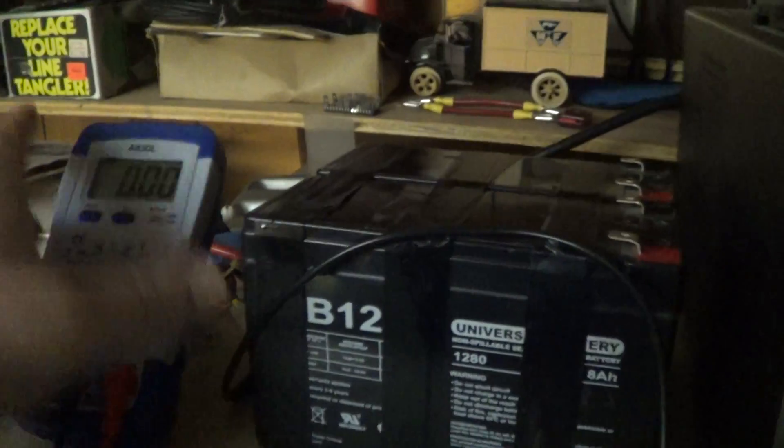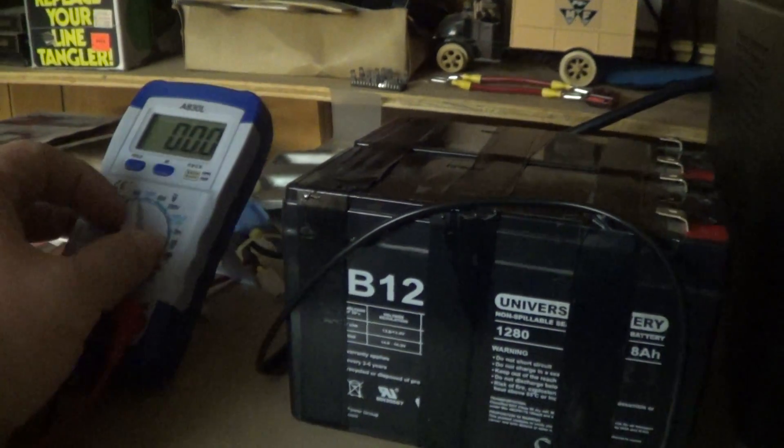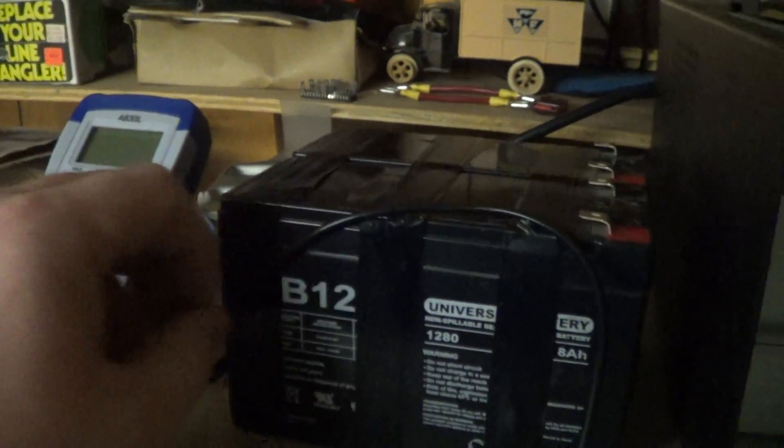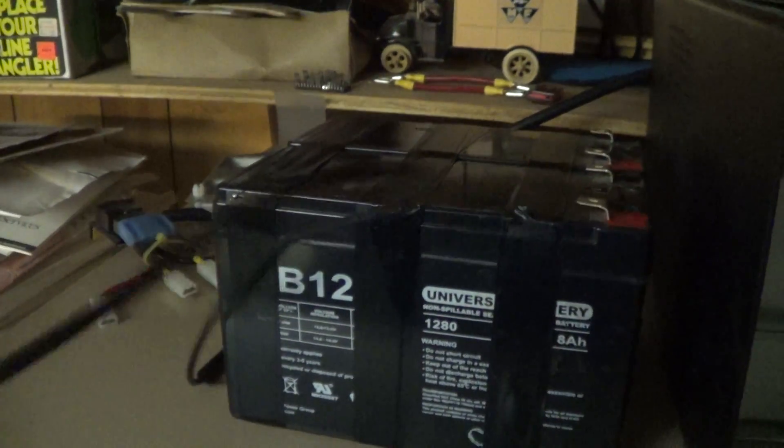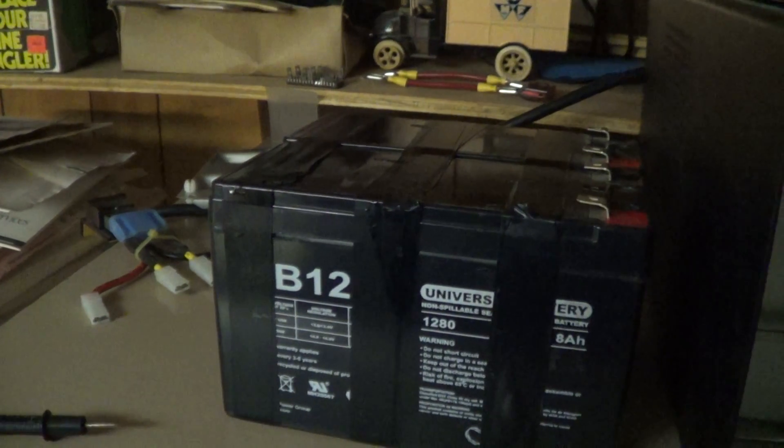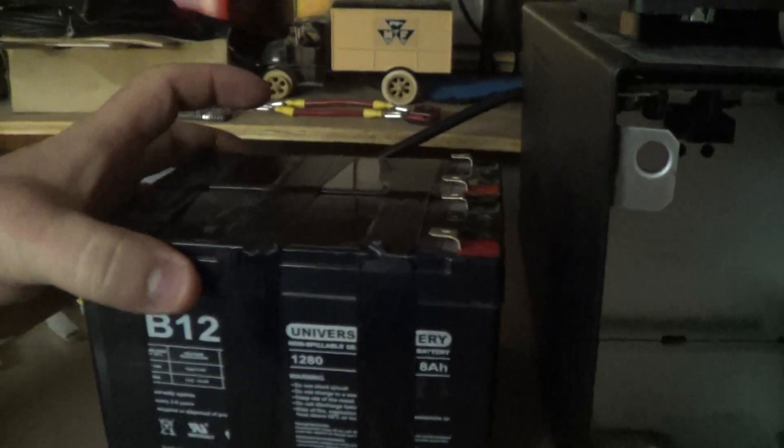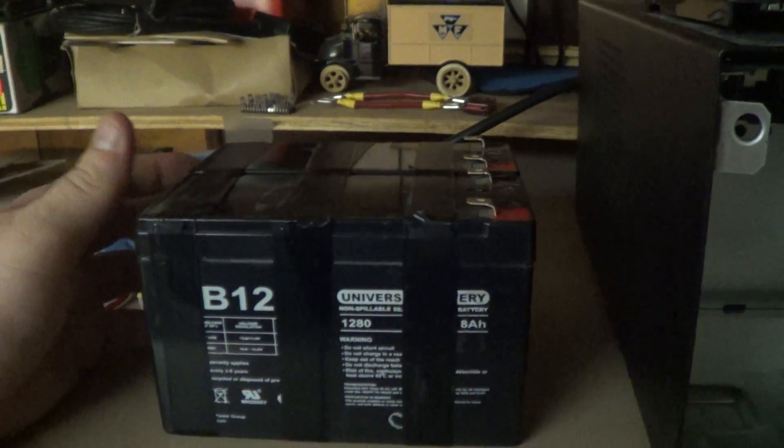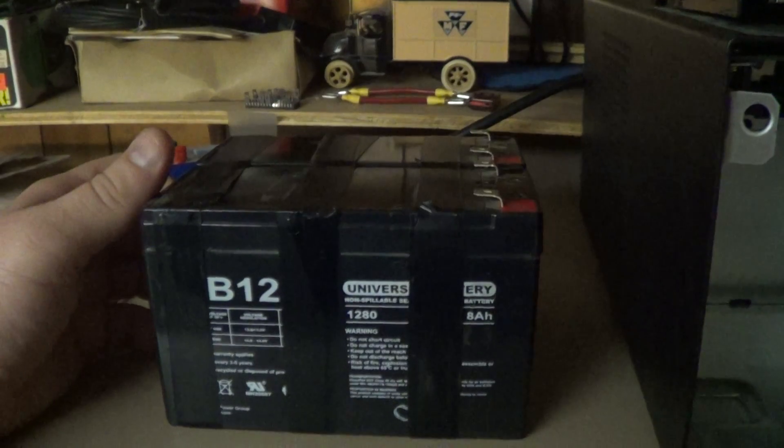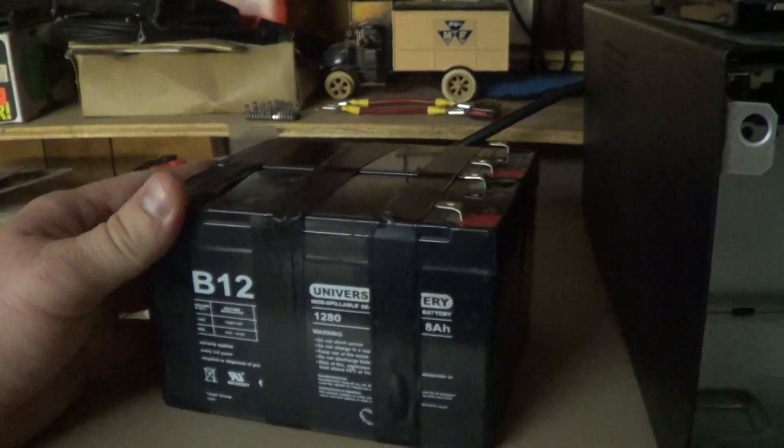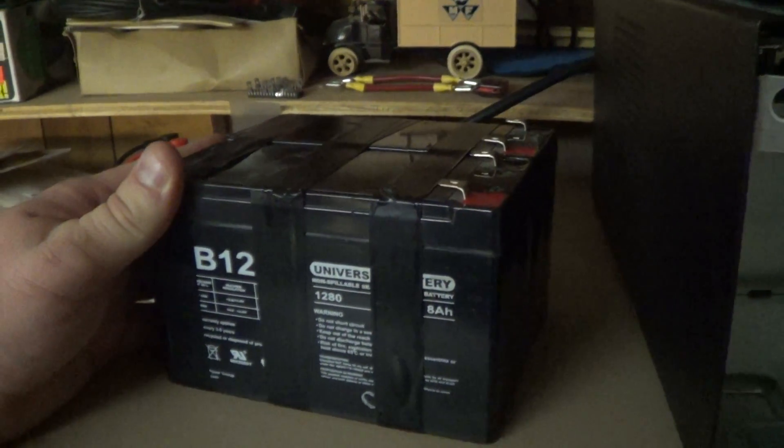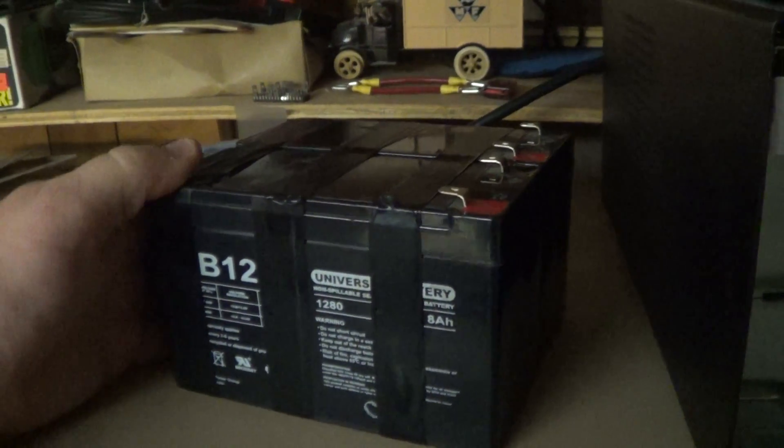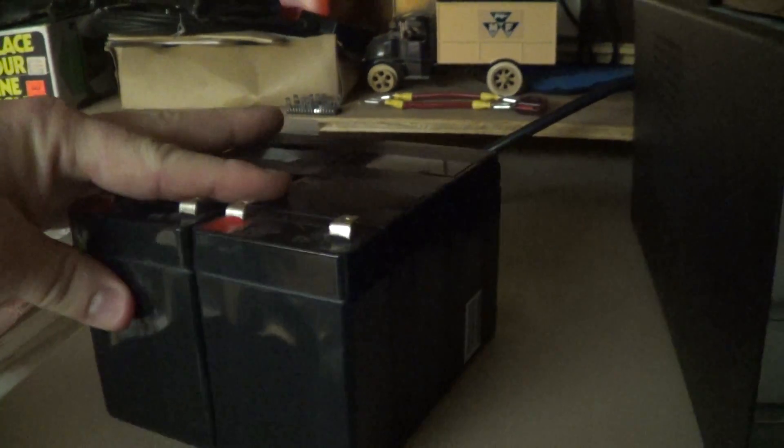Interestingly enough, this is not the first time I've had this happen. These are UPG, universal power group batteries. They don't have the greatest reputation in the world. And I actually was running a set of these in a regular back UPS and they failed in exactly the same way. And I just thought that was interesting, the way the UPS behaved and the way these batteries happen to fail.